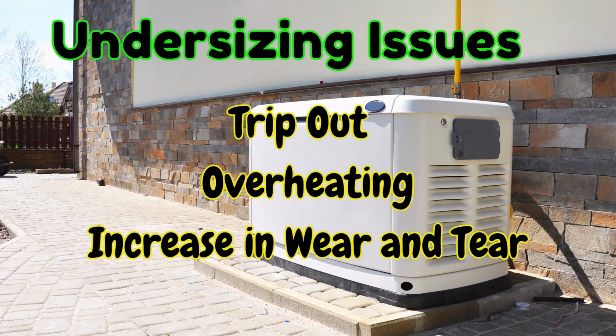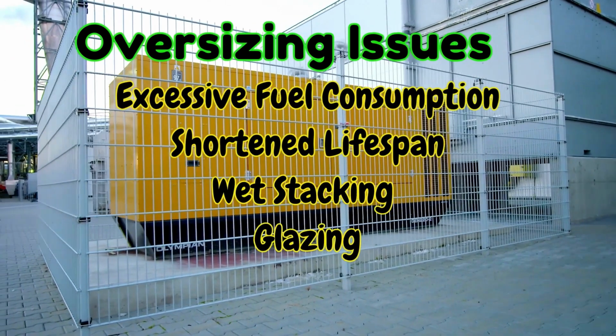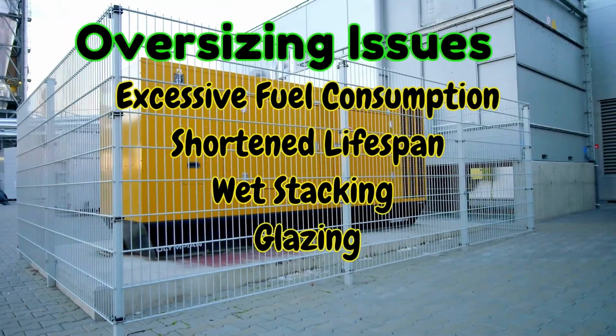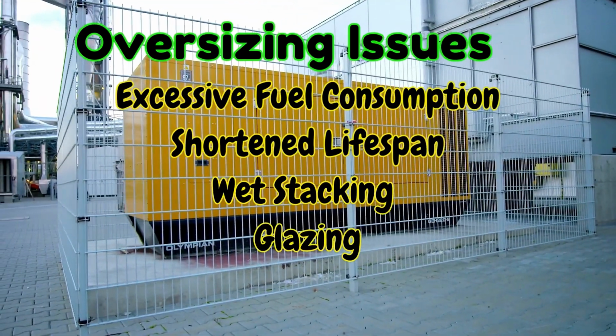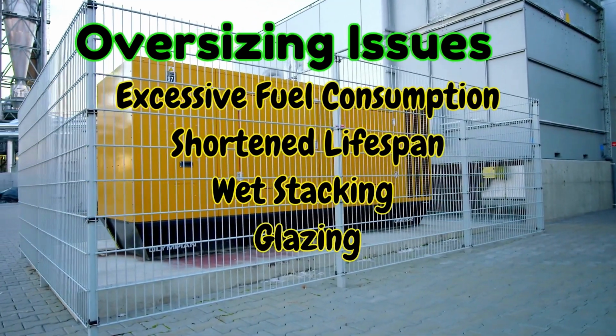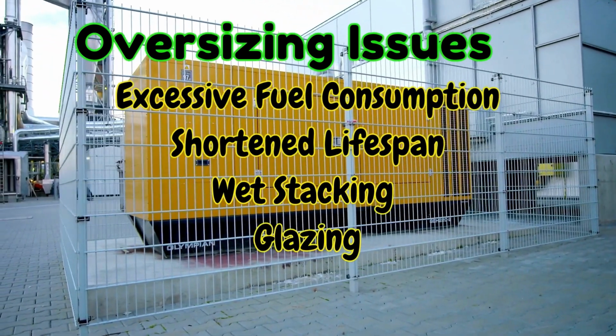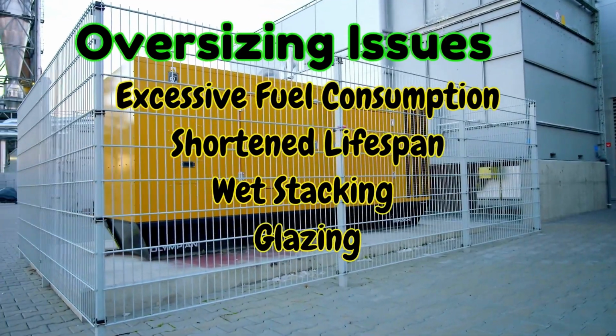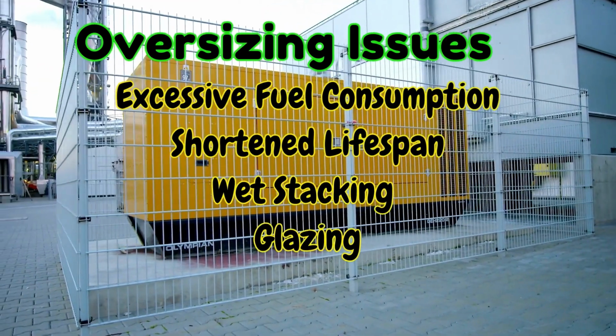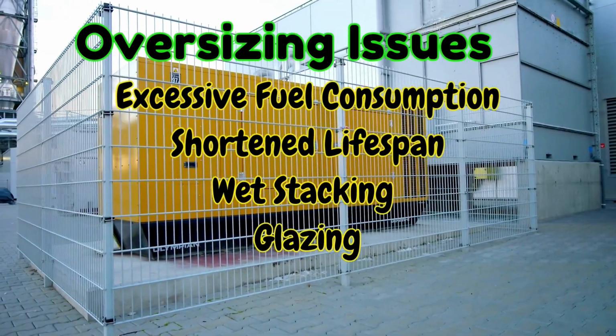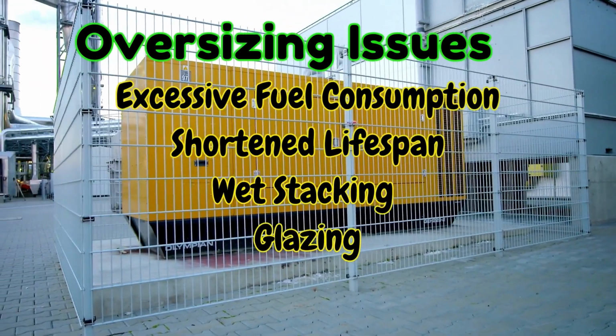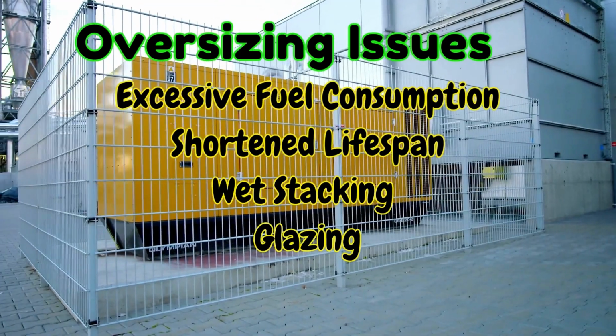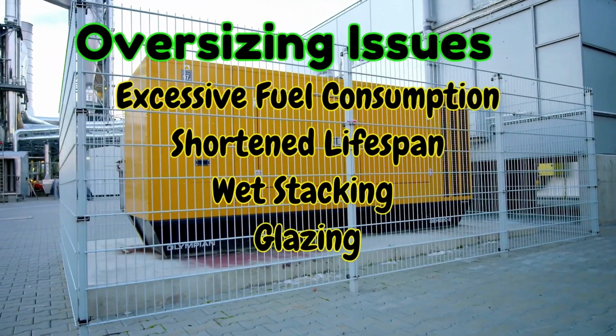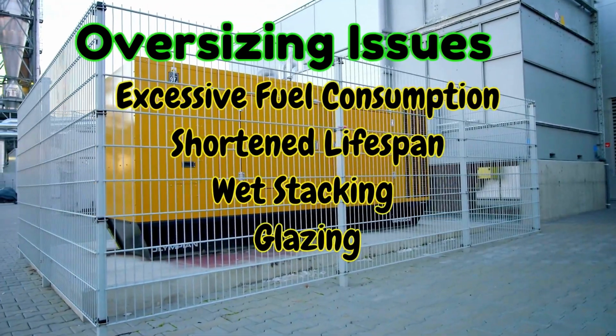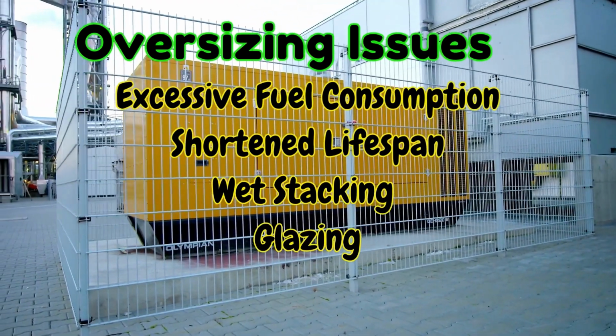But on the other hand, oversizing a generator can lead to: number 1, excessive fuel consumption; number 2, a shortened lifespan; number 3, wet stacking. Wet stacking occurs when unburnt fuel accumulates in the exhaust system, reducing the generator's efficiency and potentially causing damage. And then lastly, number 4, glazing. Insufficient load can lead to glazing in diesel engines, causing a buildup of carbon deposits and reduced engine efficiency.